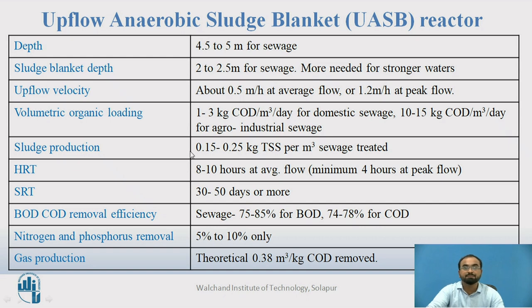SRT is typically kept around 30 to 50 days or more. BOD and COD removal efficiency is around 75 to 85 percent and 74 to 78 percent respectively. Nitrogen and phosphorus removal efficiency is very low at around 10 percent only. Gas production is typically around 0.38 cubic meters per kg COD removed.